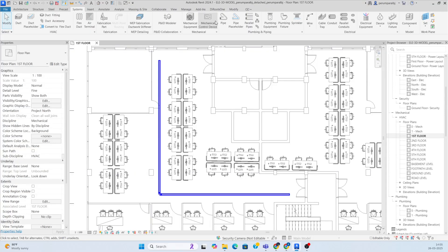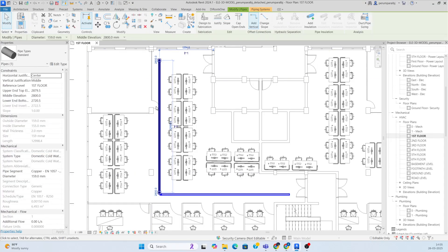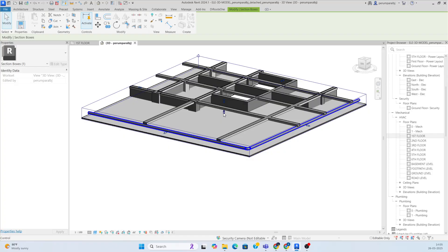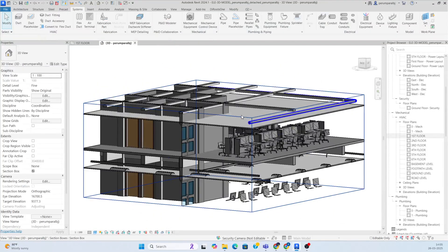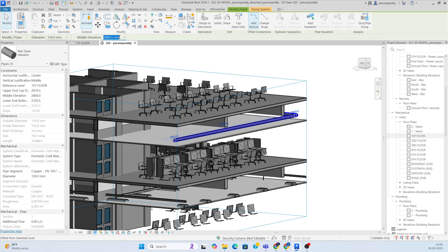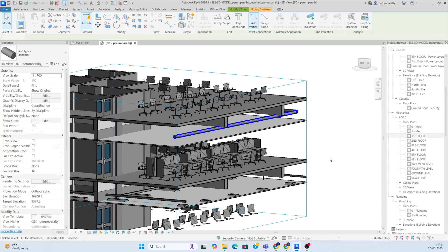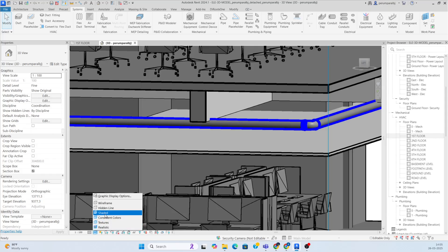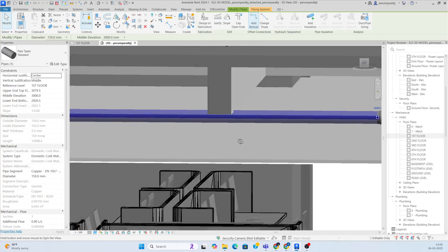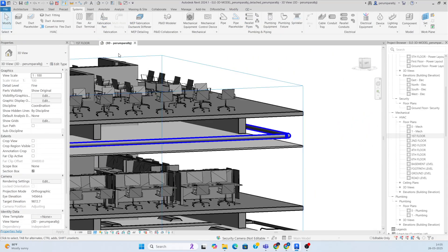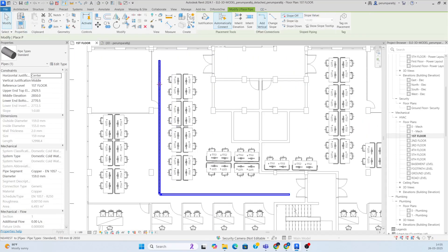You can also check the 3D view to see how it looks — the pipe is showing above the ceiling. If you want to move it up, change the elevation. I set it to 3000, but it is clashing with the structural beams, so I reduced it to 2850.